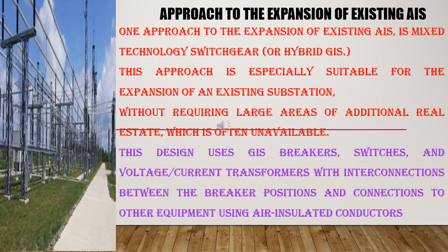Approach to the expansion of existing AIS. One approach to the expansion of existing AIS is mixed technology switchgear or hybrid GIS. This approach is especially suitable for the expansion of an existing substation without requiring large areas of additional real estate, which is often unavailable. This design uses GIS breakers, switches, and voltage and current transformers with interconnections between the breaker positions and connections to other equipment using air-insulated conductors.